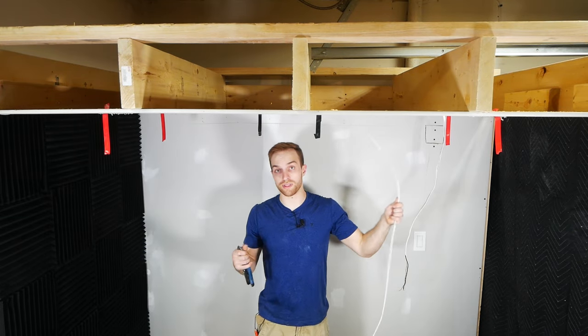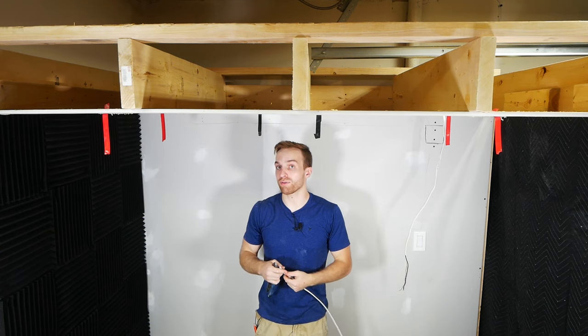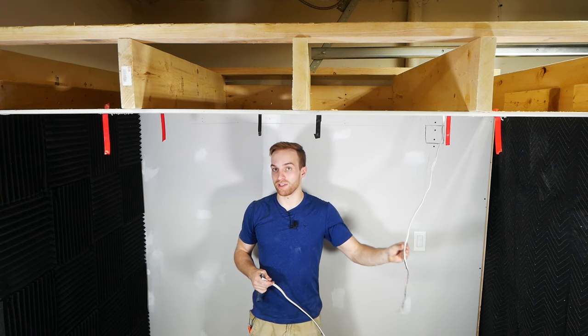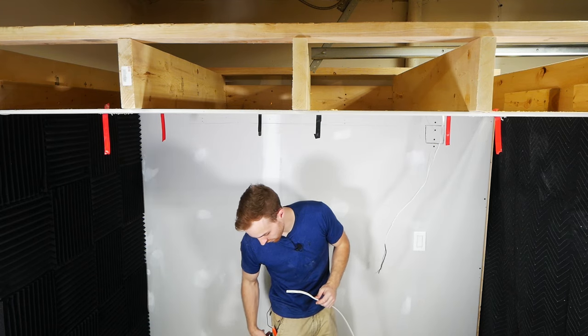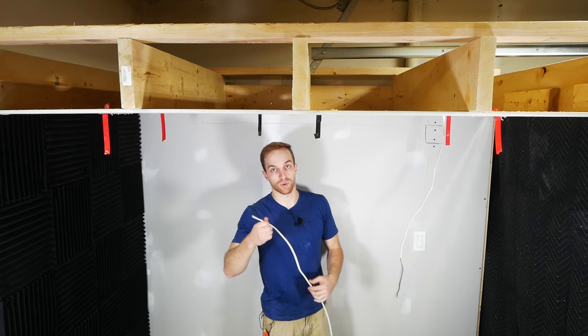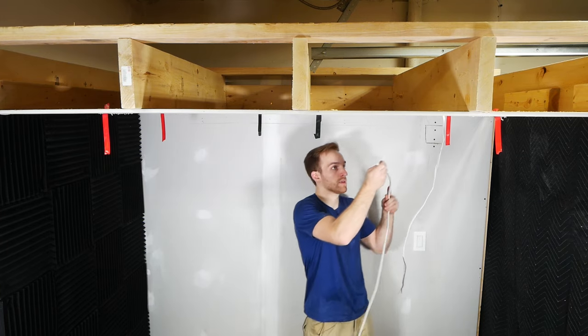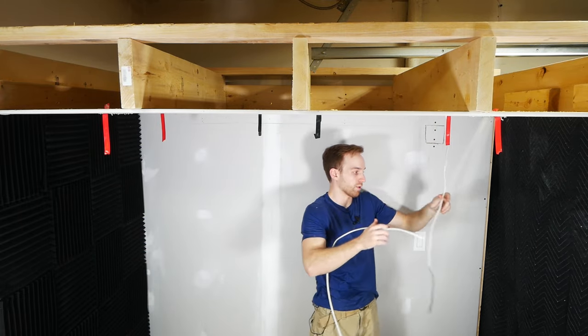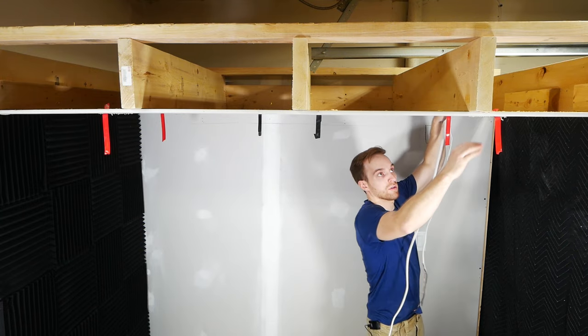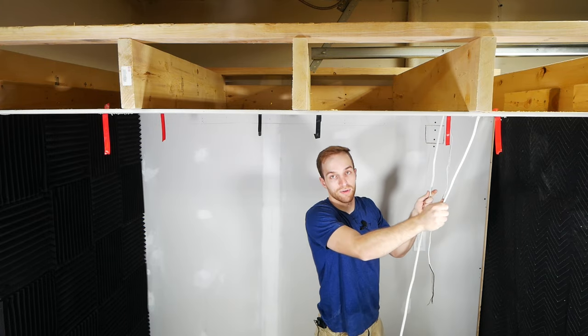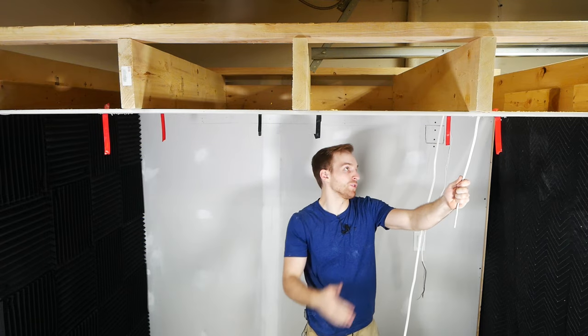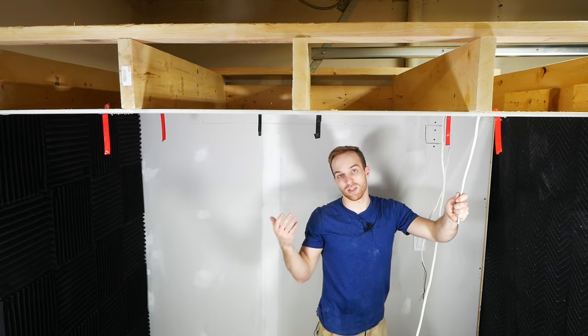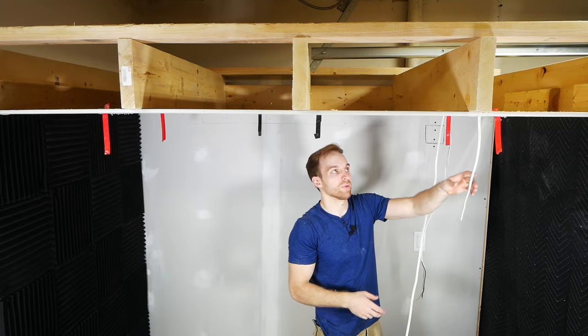To loop these, I'm going to be using 14/2 Romex. If the breaker that you turned off to work on this circuit was rated at 20 amps, you would want to be using 12/2. Again, though, this is all going to vary by your local code. Here where I'm located, this is almost always done with 14.2. It's usually just a 15 amp circuit. So of course, these two, very straightforward for me to simply run a wire between them. Now the only reason why you might have some trouble here is if there's a cross piece. And that's not an issue at all. You can easily see both sides of it. It's not often things are ran on them anyways. So you can just drill an additional hole and run your wire through that hole.